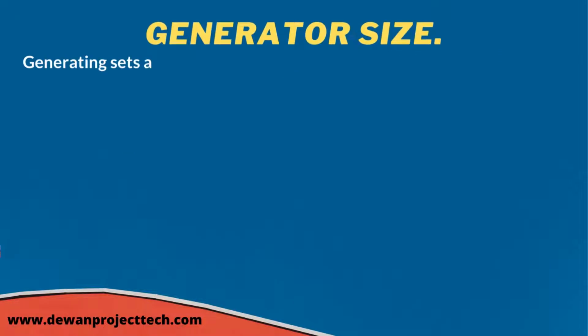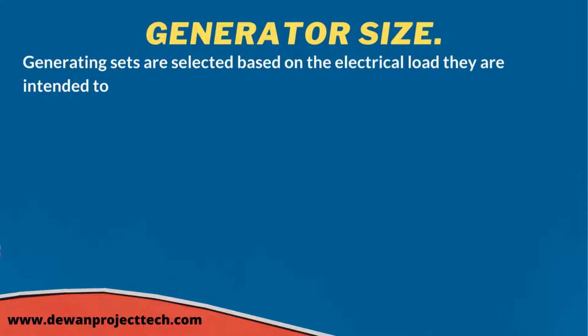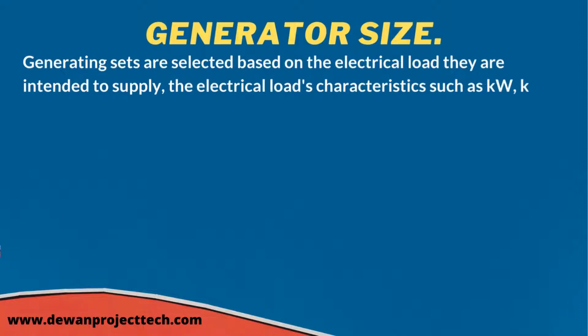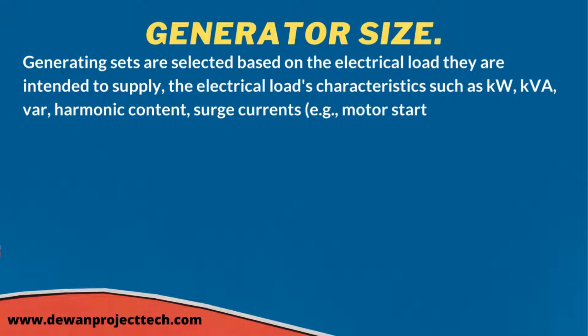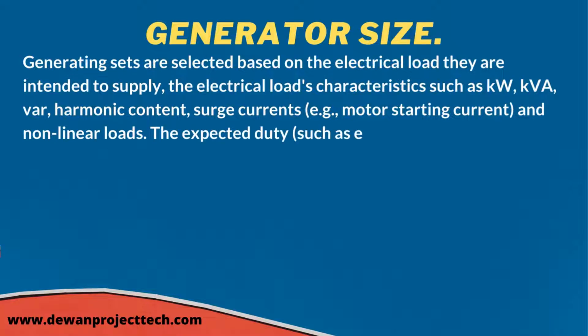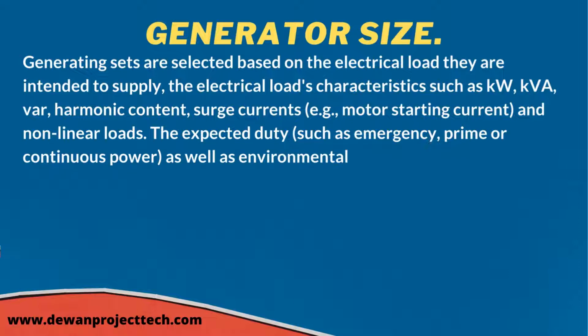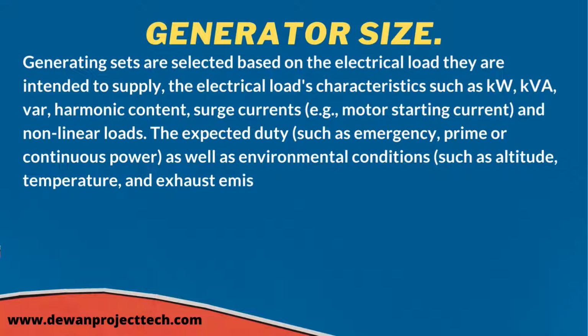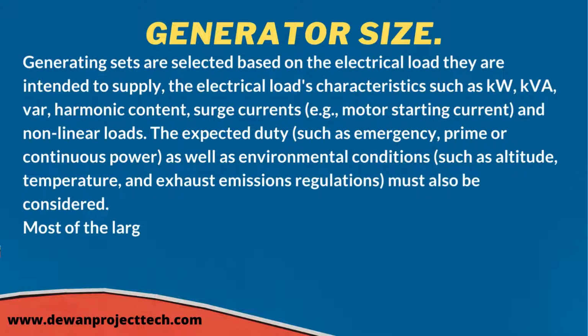Generator size: generating sets are selected based on the electrical load they are intended to supply. The electrical load's characteristics such as kW, kVA, kvar, harmonic content, surge currents, for example, motor starting current, and non-linear loads. The expected duty, such as emergency, prime or continuous power, as well as environmental conditions, such as altitude, temperature, and exhaust emissions regulations, must also be considered.